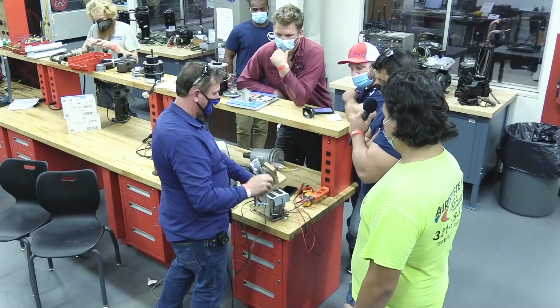Moral of the story is, it takes high voltage, steps it down to low voltage. Your amperage does not mean power and your voltage does not mean power. If you're replacing a transformer, it's important to match up your voltage coming in and your VA, okay? It's an electromagnet, inductive load. I'm inducing an electromagnetic field, and that electromagnetic field is being induced into the secondary coil. So who was it that asked about low voltage circuitry? Was it you? Okay, so does that help a little bit? So don't be afraid of the volts and the amps. You need to be thinking, this is my new source. I'm starting out with approximately 24 volts here.